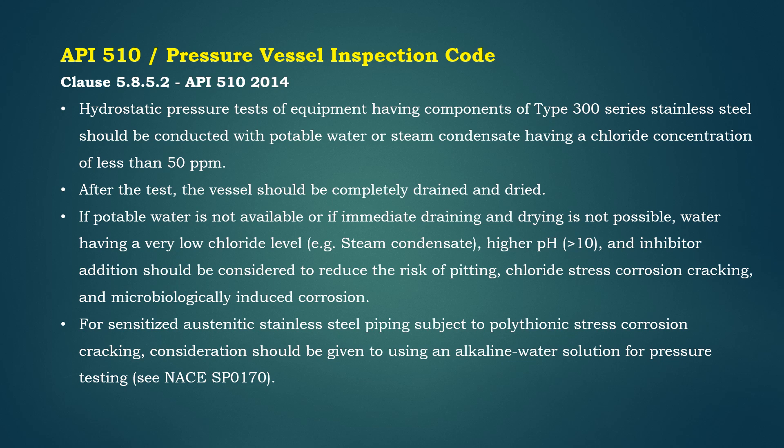If potable water is not available, or if immediate draining and drying is not possible, water having a very low chloride level, a higher pH of greater than 10, and inhibitor addition should be considered to reduce the risk of pitting, chloride stress corrosion cracking.